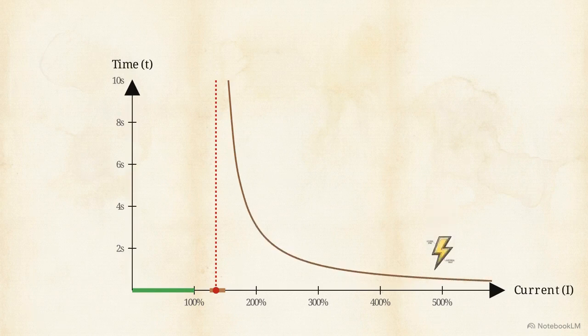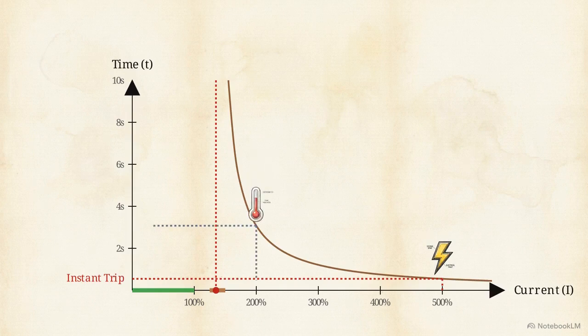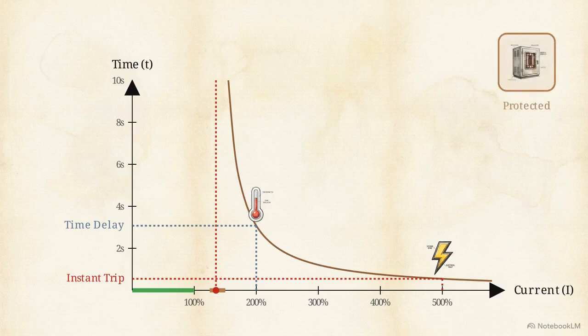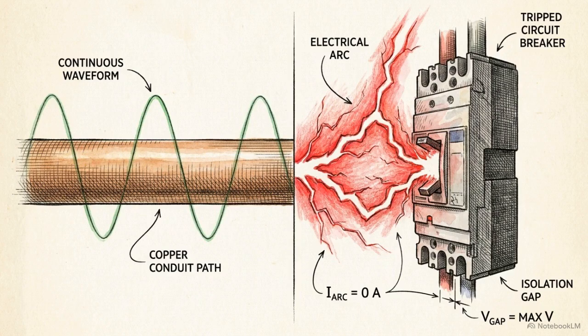We then apply an inverse time characteristic to this setting. This logic ensures that massive fault currents are cleared almost instantly, while smaller overcurrents are given a slight time delay. A mathematically precise overcurrent relay ignores standard operational spikes, but instantly isolates catastrophic short circuits before they destroy the windings. For large industrial units, typically those exceeding 5 megavolt amperes, we require a final, highest-tier layer of protection.